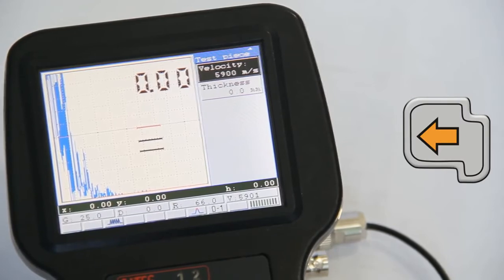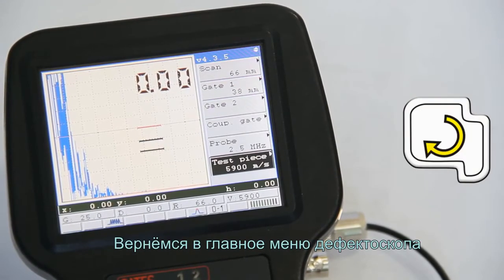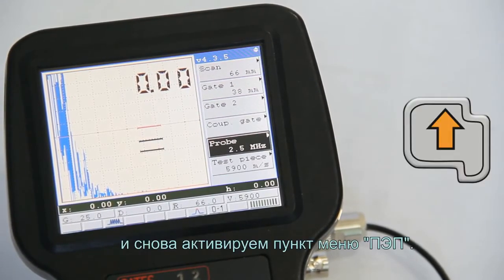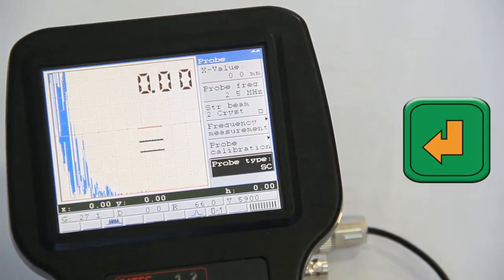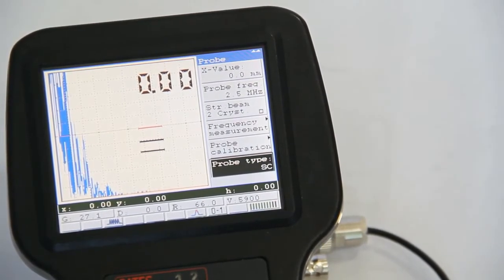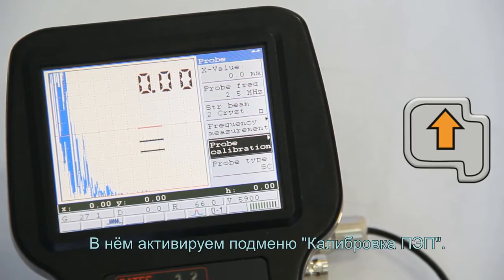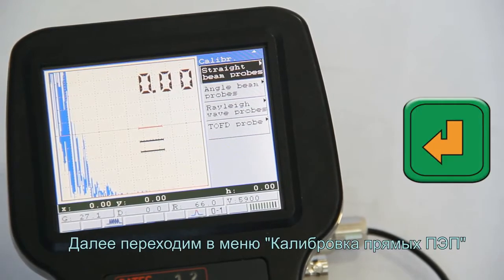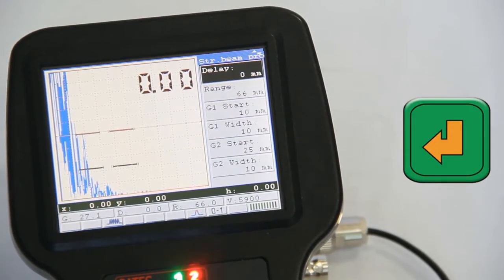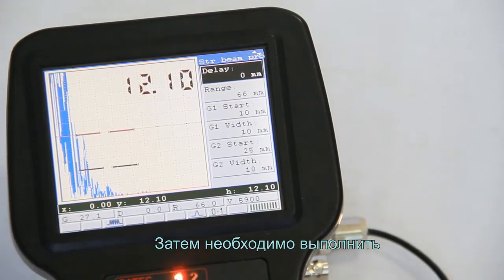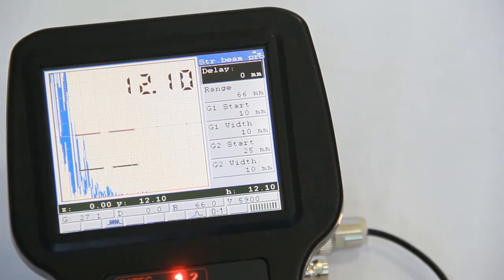Return to the main menu of the flaw detector and again activate the probe menu item. Here activate the probe calibration submenu. Then move to the straight beam probes menu. Then perform the following actions. Place the probe on the prepared surface of a block.